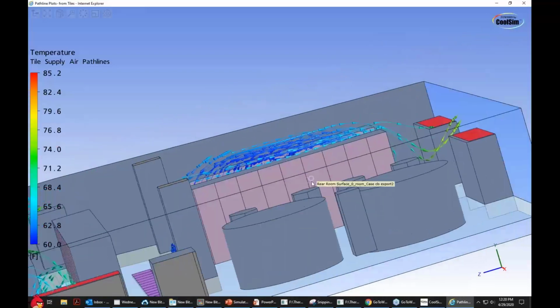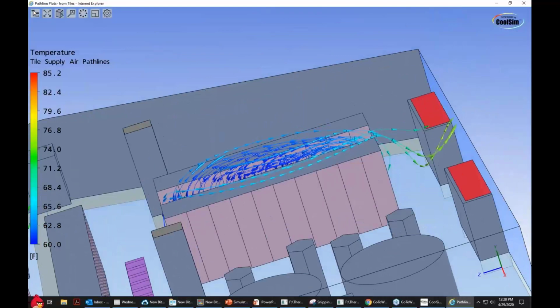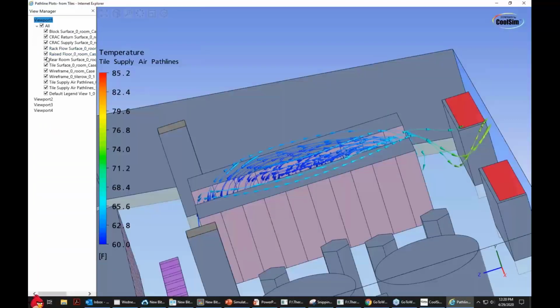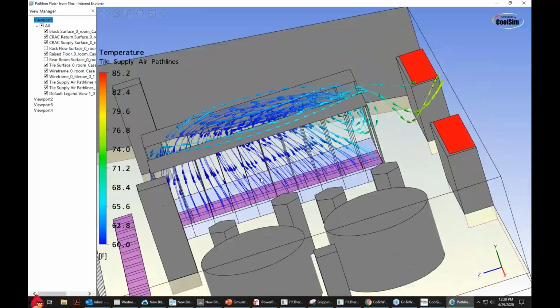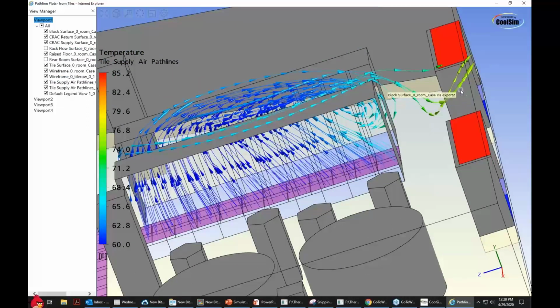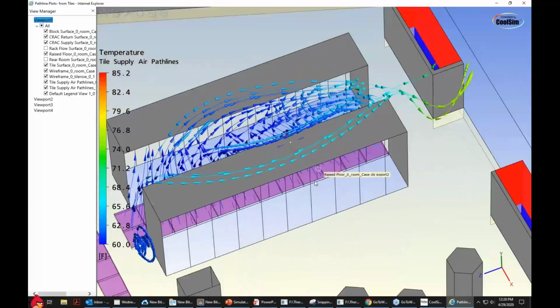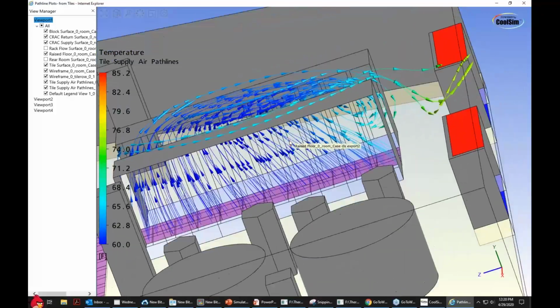Furthermore, we've got problems over here. We're a little too close. In CoolSim, you have this nice ability to remove some of the surfaces so that you can see. And I'm just going to turn off my racks here so that you can see what's going on behind. And you see right there the Bernoulli effect happening. So you've got very high-speed air coming down under the floor, coming along from that CRAC unit and bending. So these racks are starving at the top for cool air because the air, due to momentum, is going that way. So that's a good illustration of putting your racks too close to your cooling units.